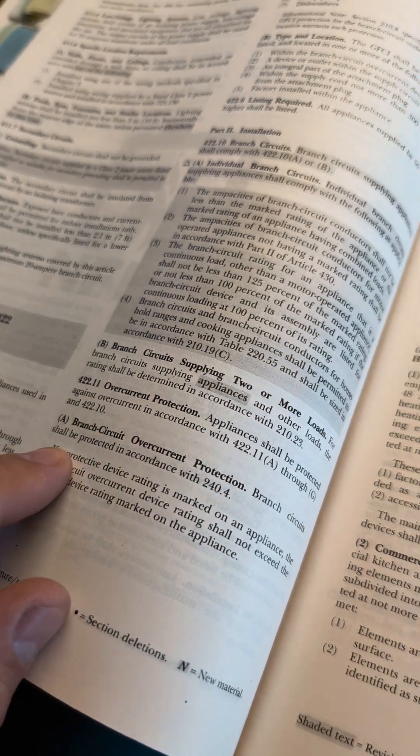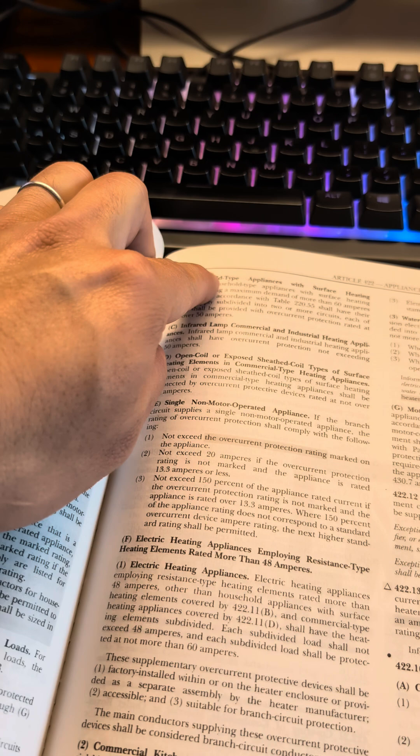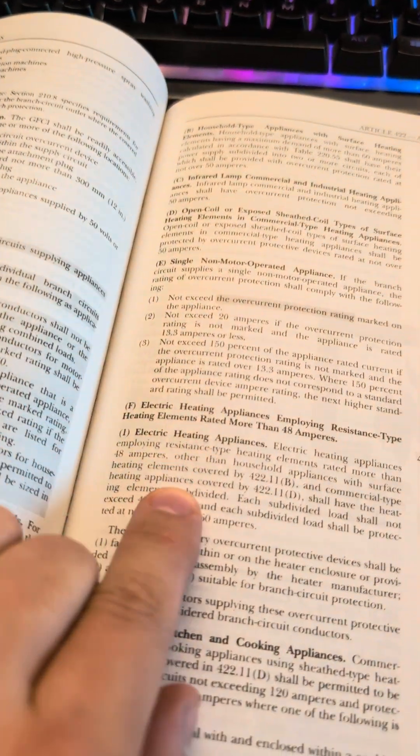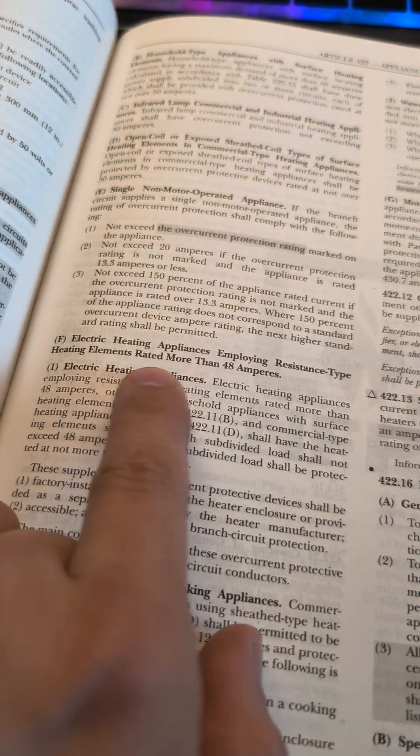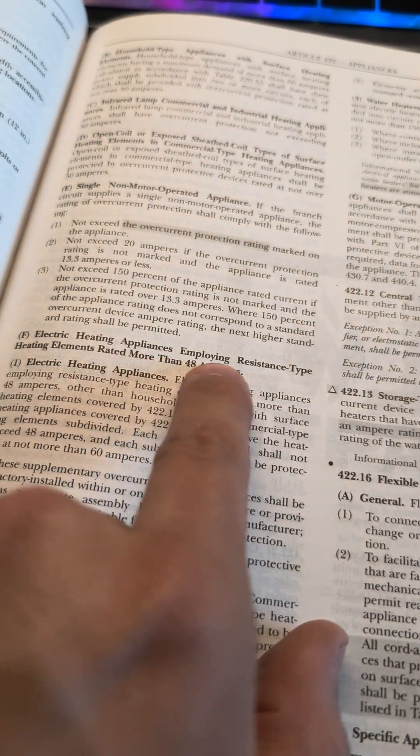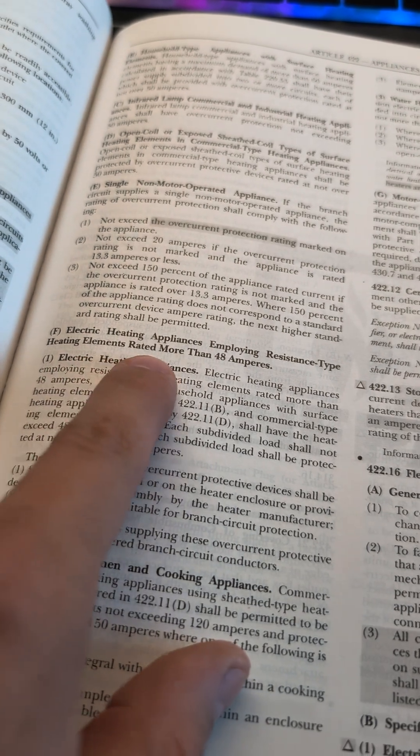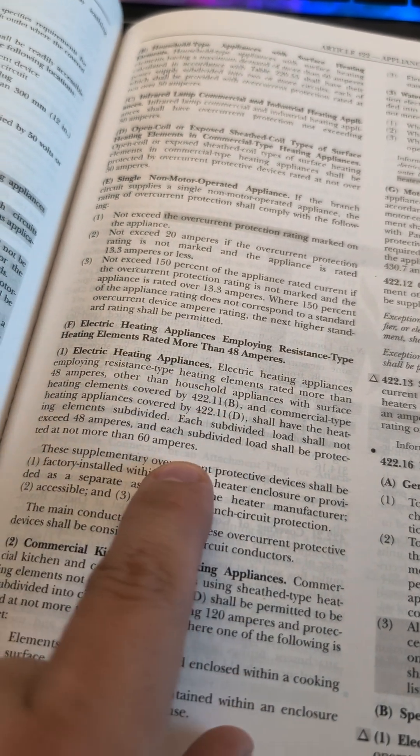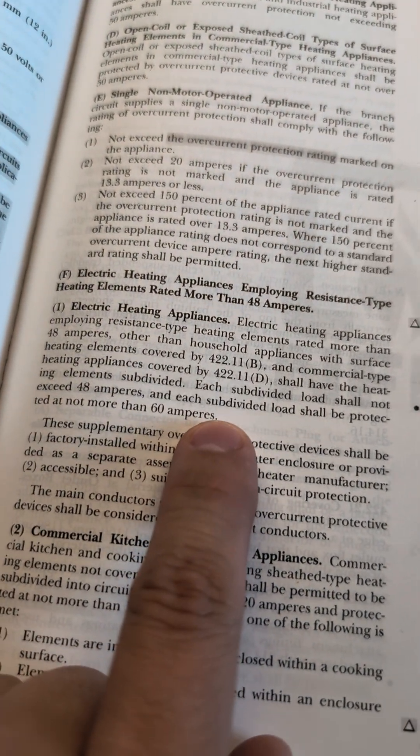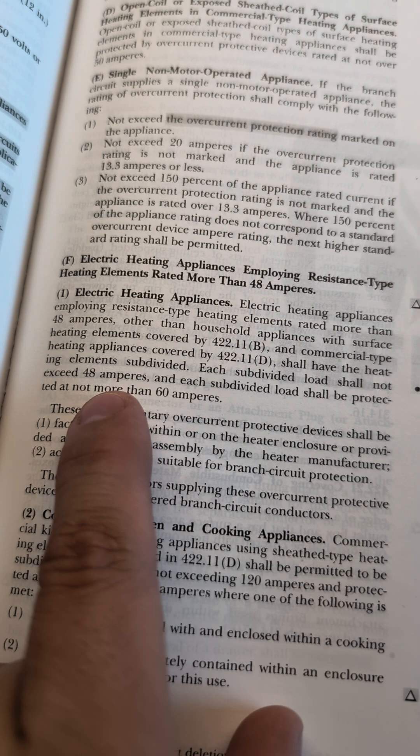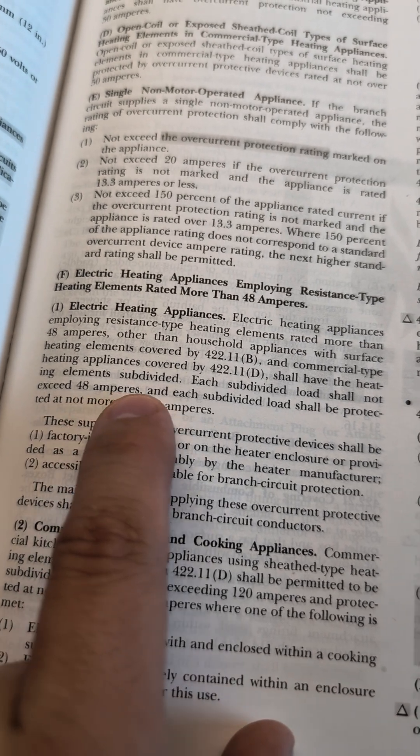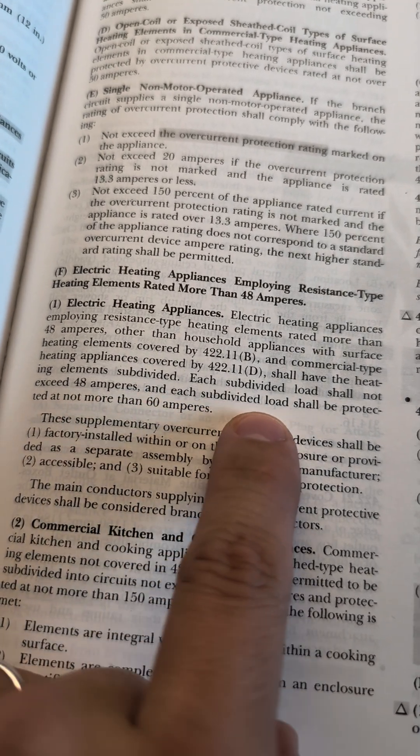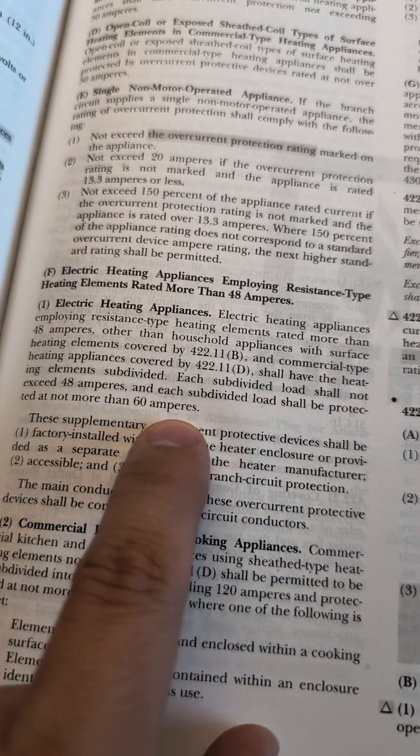And now we can start to look for resistance type heating elements. Section F. Heating appliances employing resistance-type heating elements. Perfect. And then the last sentence here says each subdivided load shall not exceed 48 amperes and each subdivided load shall be protected at not more than 60 amps.